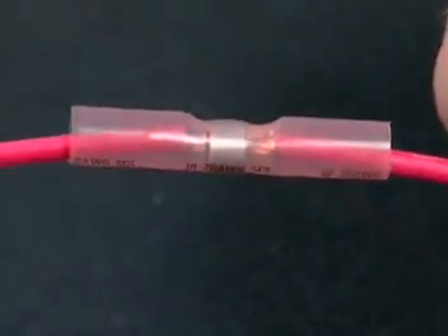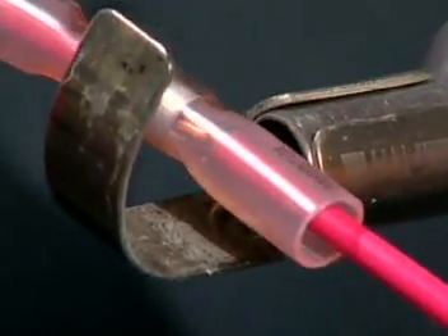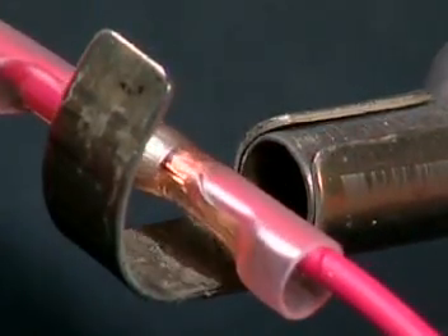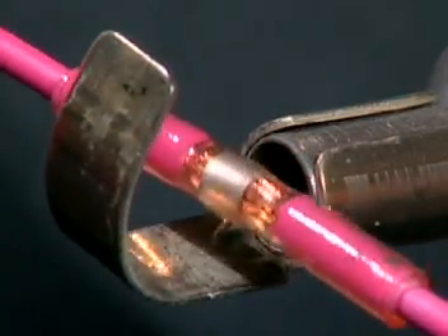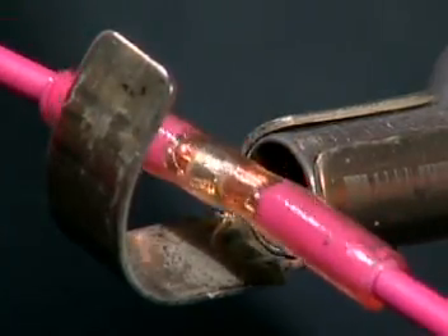Center the soldering ring over the intermingled wire strands. Heat the connector evenly from the center out to the ends until the tubing is fully recovered. Continue to distribute the heat over the solder sleeve. Do not concentrate the heat too long in one place. After the solder flows, remove the connector from the heat and let it cool.